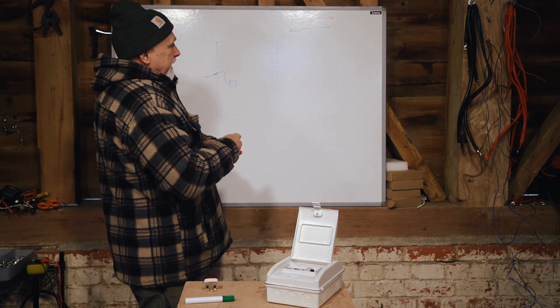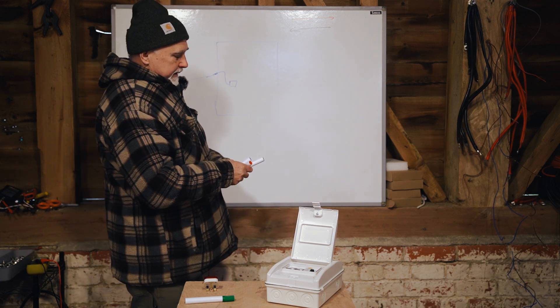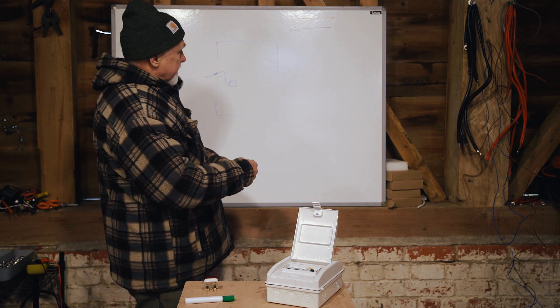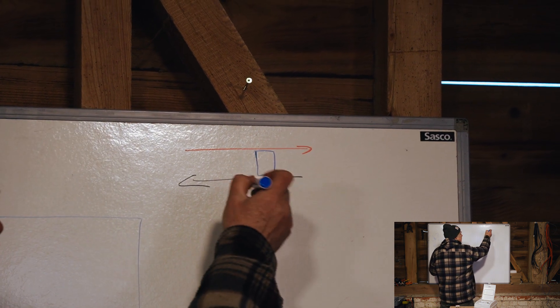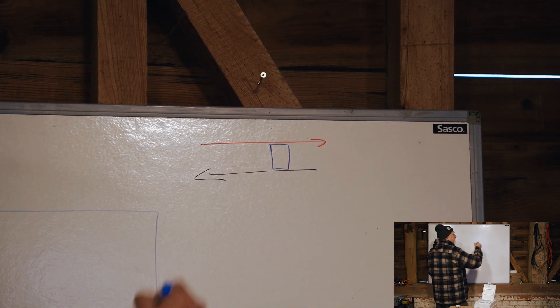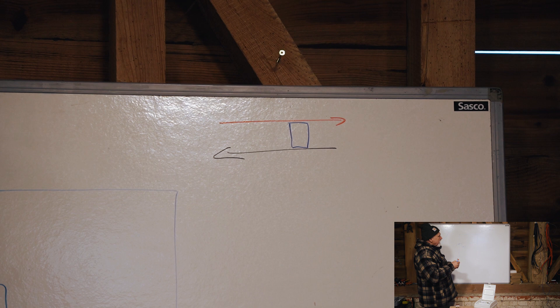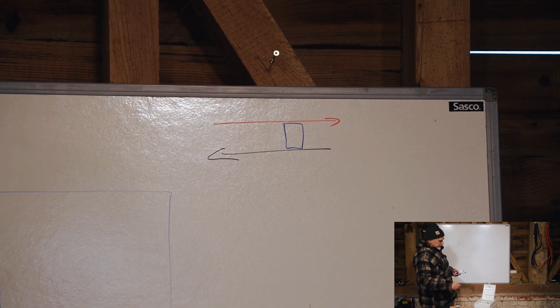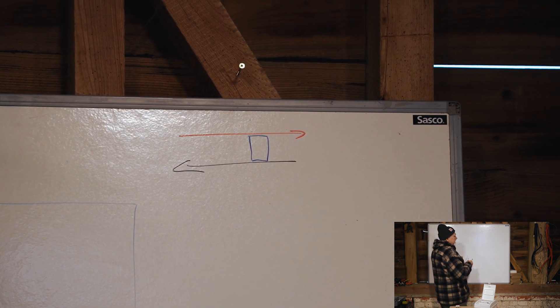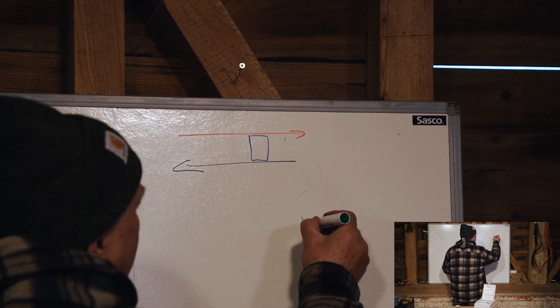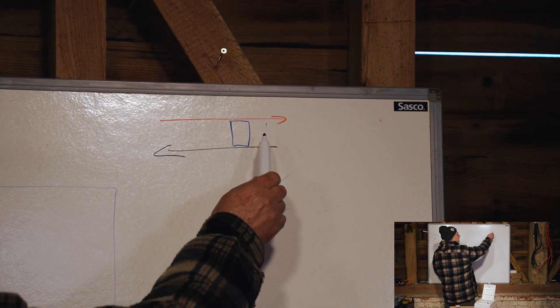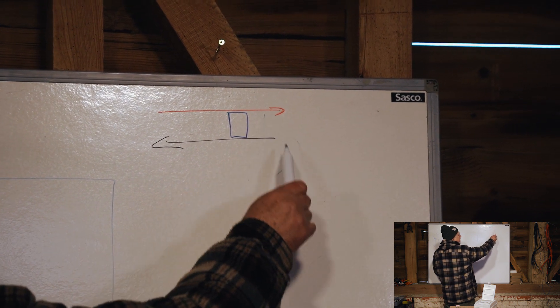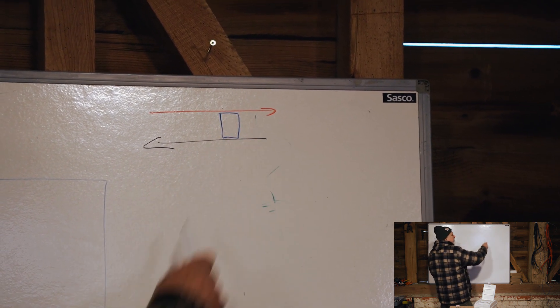Then, basically, what the RCD does is it sits between them. So I'll use blue again. It sits between them here and it measures the difference in the current that's going out versus the current that's coming in. And the whole idea is that if somehow you've got something coming down to earth here, then what it's going to do is it's going to detect that there's a leakage going to earth and it's going to actually switch everything off.